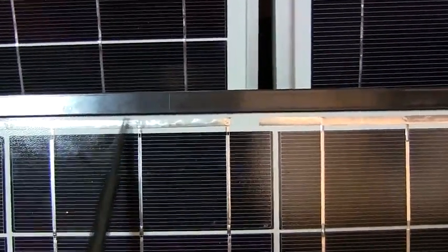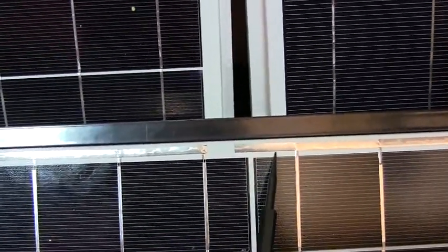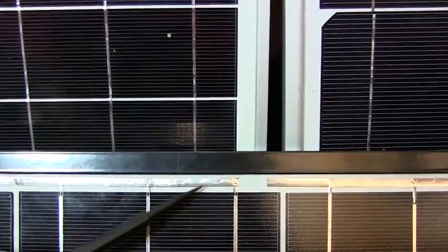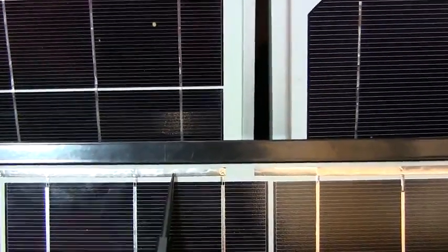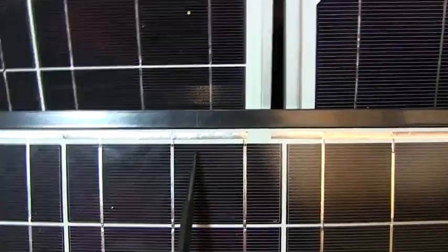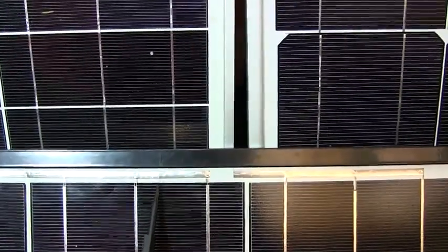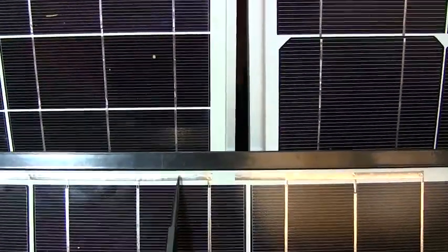So if we go and have a look, these metal tabs over here are the flat metal tabs which link the actual silicon cells together. So they run as ribbons right through the solar panel, linking all the cells together. But as you can see, where they come up to the frame, there's not much gap between the frame, and if you have a high voltage going through these, you've got a potential problem. Now this panel is a 55 watt panel, so you wouldn't think that you'd have these in a large array on your roof. But it's something to look out for. If you have a 250 watt panel where this gap is small, that is a potential no-no.